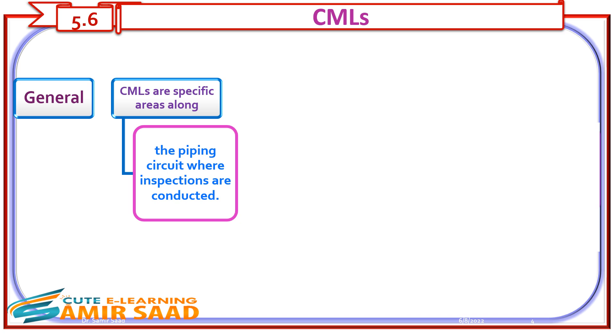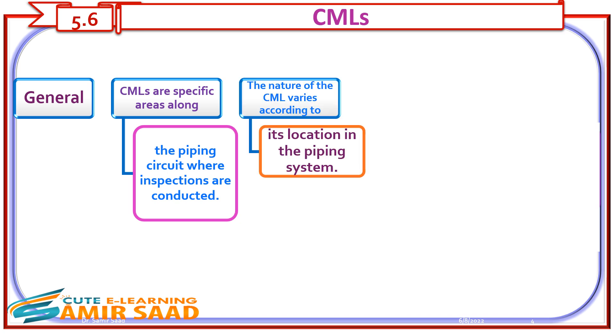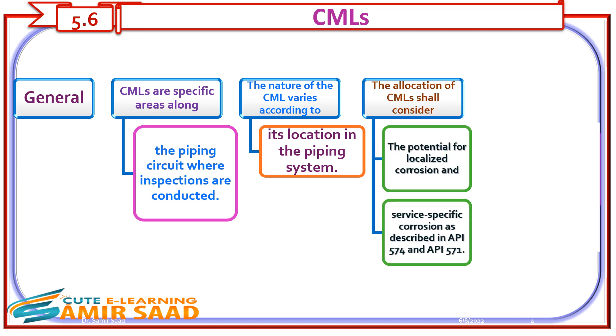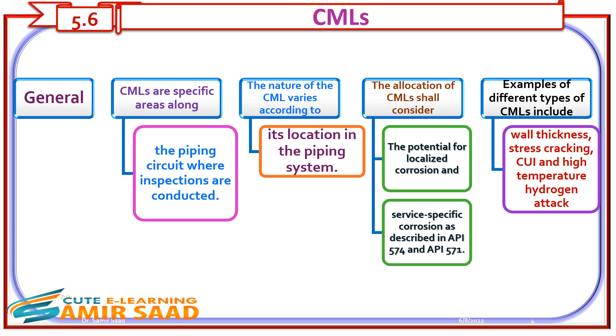General CMLs are specific areas along the piping circuit where inspections are conducted. The nature of the CML varies according to its location in the piping system. The allocation of CMLs shall consider the potential for localized corrosion and service-specific corrosion as described in API 574 and API 571. Examples of different types of CMLs include wall thickness, stress cracking, CUI, and high-temperature hydrogen attack.